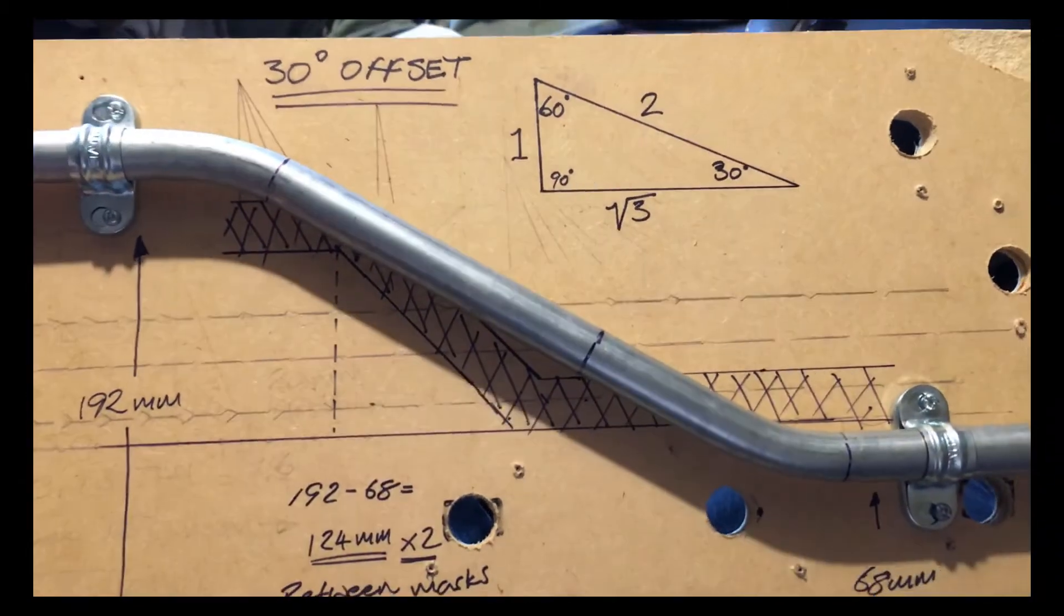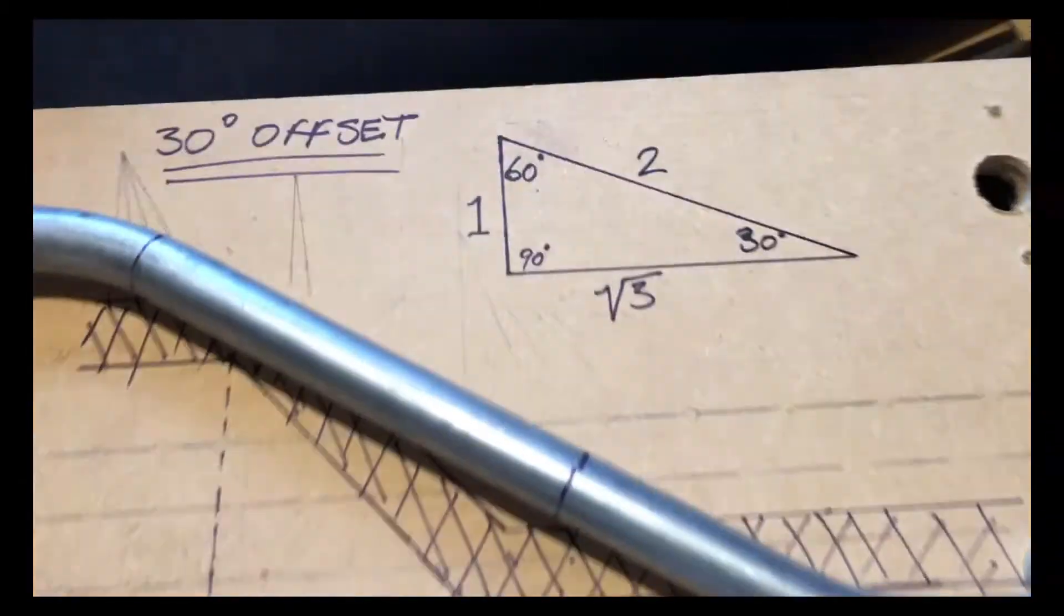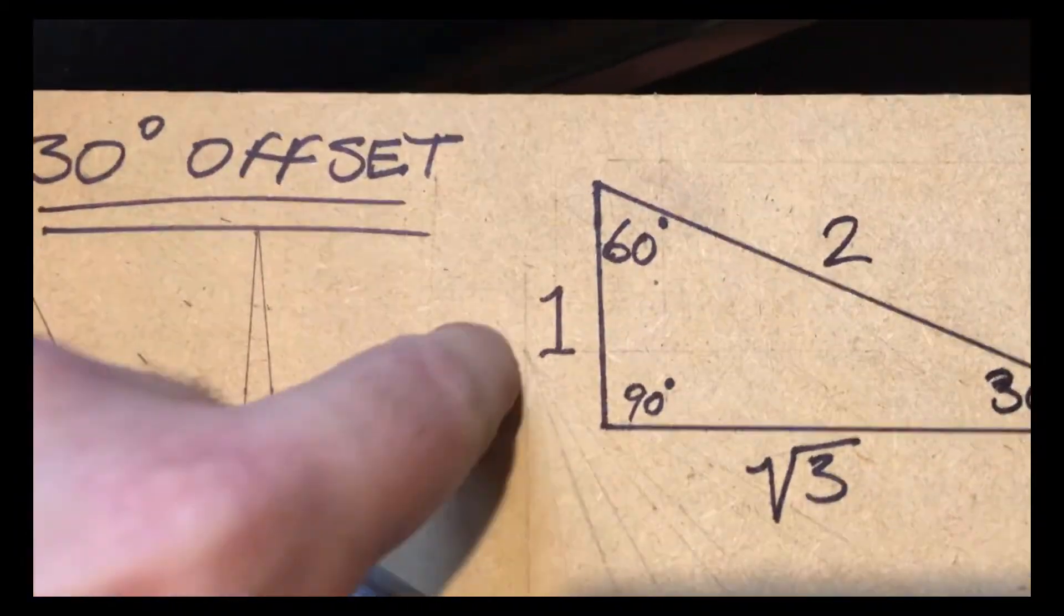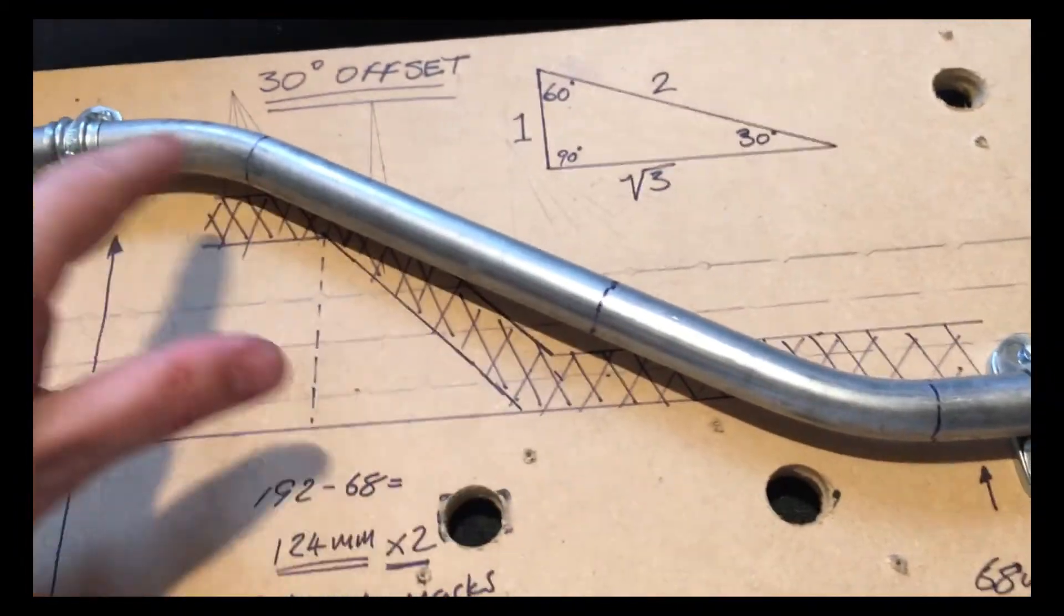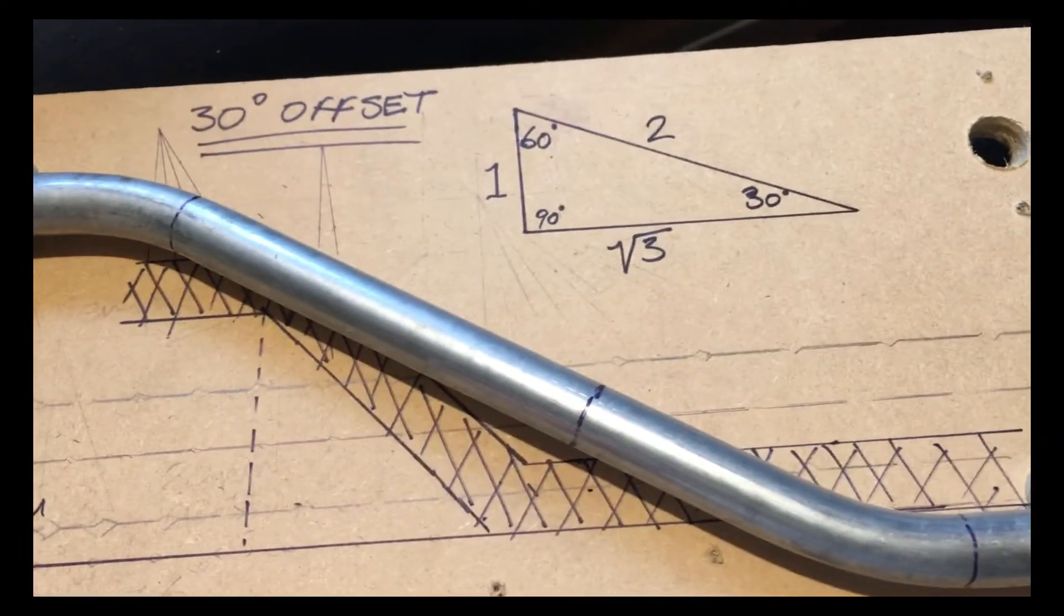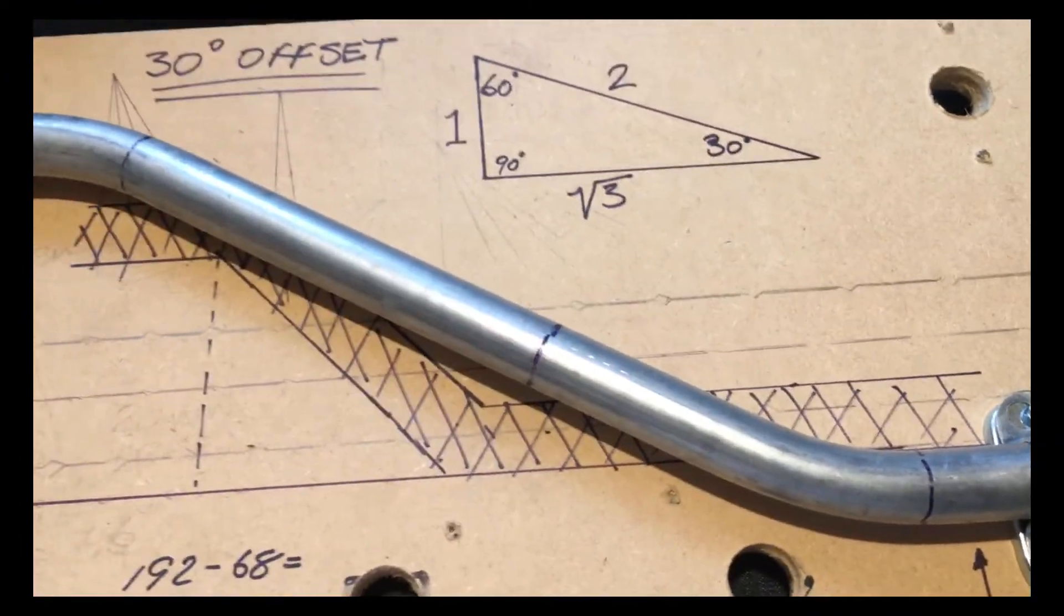Remember, to find this distance that you want to go over, multiply it by two, and that will give you a 30-degree bend.